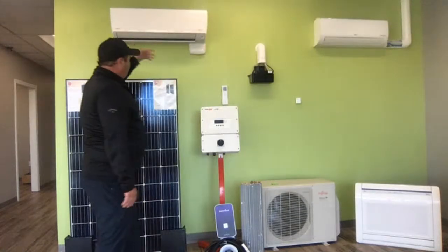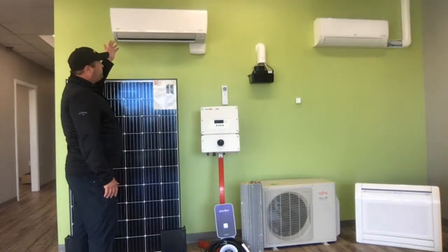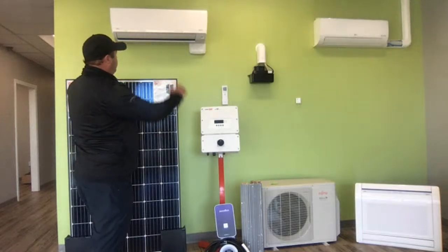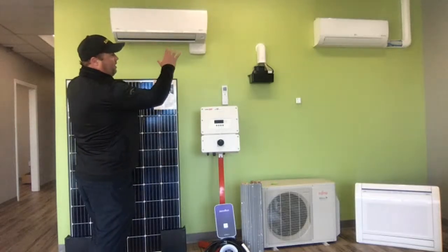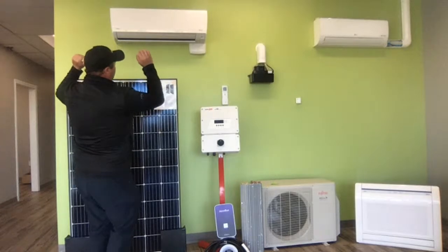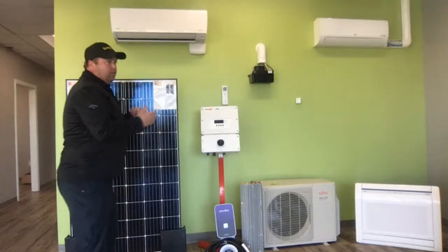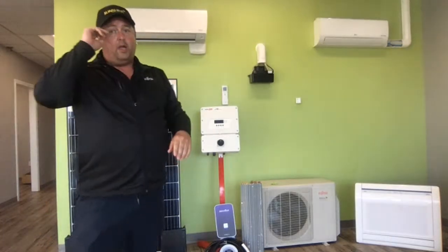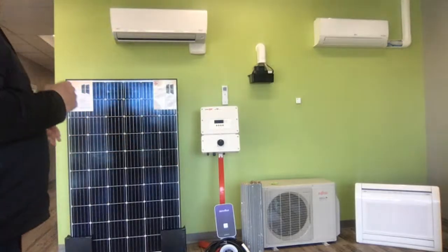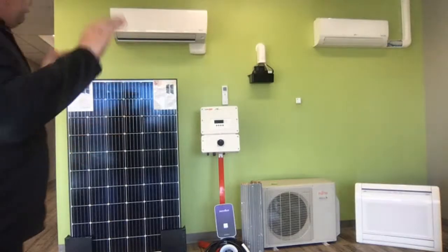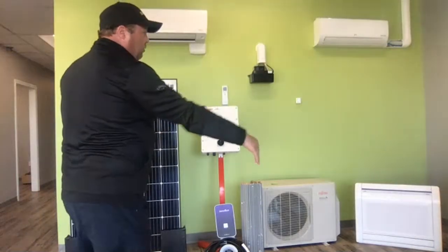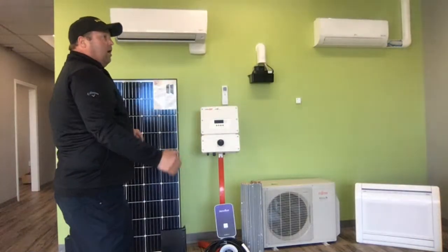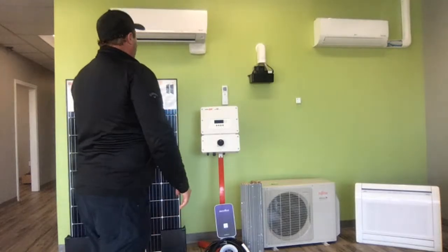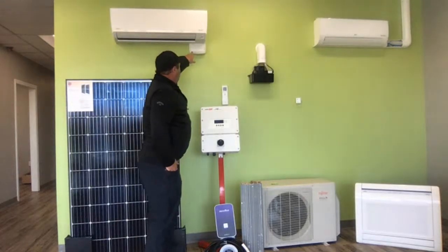So when we're installing these heat pumps, basically what you're doing is you're typically on an outside wall. We're going out with our line sets, which is our supply and return refrigerant lines, our communication wire, and then our drain line as well, because that water, when you're air conditioning, has got to go out and down in order to get a gravity feed.